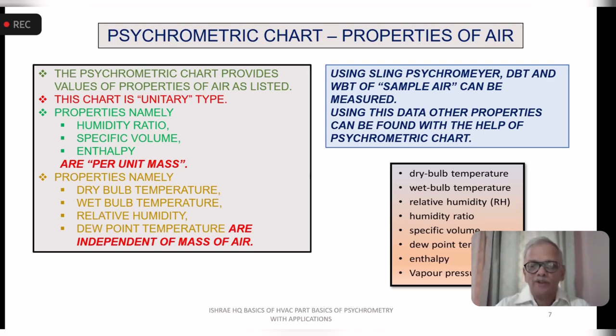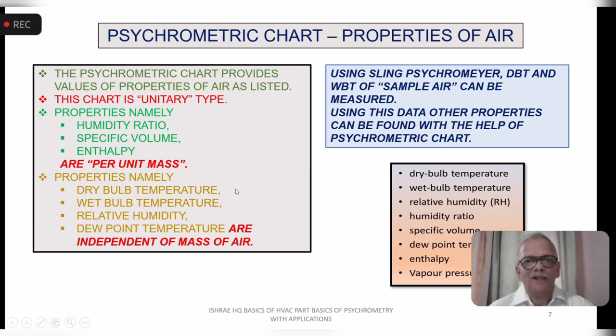And then what we are talking about is equating that. Whenever we work out the cooling load or cooling demand as the capacity required of the AC system, we are always talking about either tons of refrigeration or kilowatts. So that is the rate of heat removal. And for getting that rate of heat removal, we need to circulate a certain amount of air in terms of pounds or kilograms, and that is what will give us the desired effect. So how many cubic feet per minute or liters per second or cubic meters per hour is the circulation rate for the air has to be worked out, and that's where the psychrometric analysis helps us.